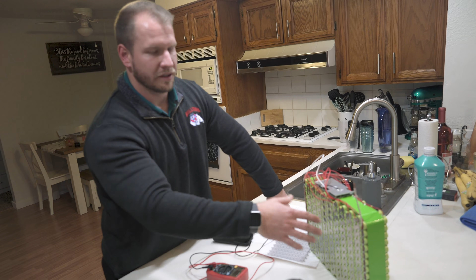What that allows you to do then is bypass the discharge amperage, which is the high one, and this is only needed for the charging, which is going to be 5 to 6 amps depending on what charger you get. The one he has right now is a 5 amp charger, so no risk at all to the battery in that, or to the BMS, battery management system, in that case.